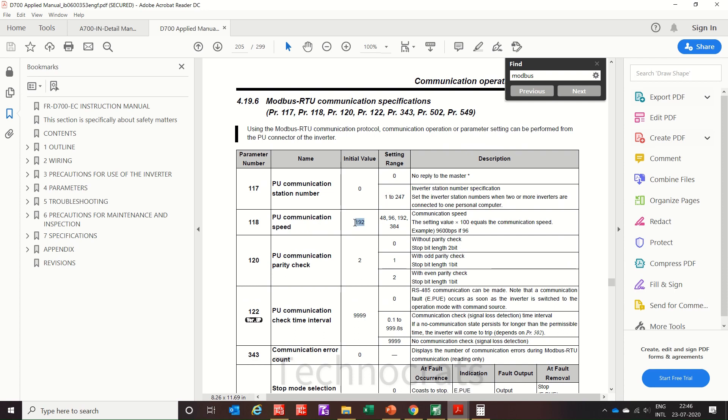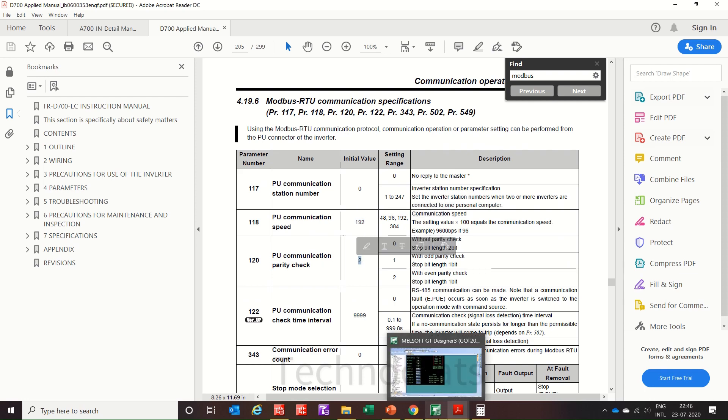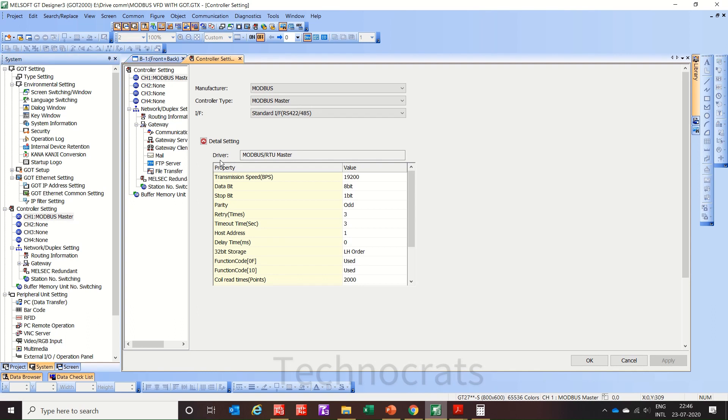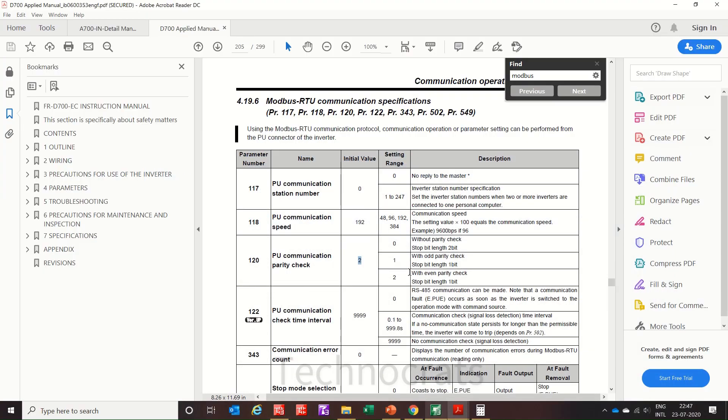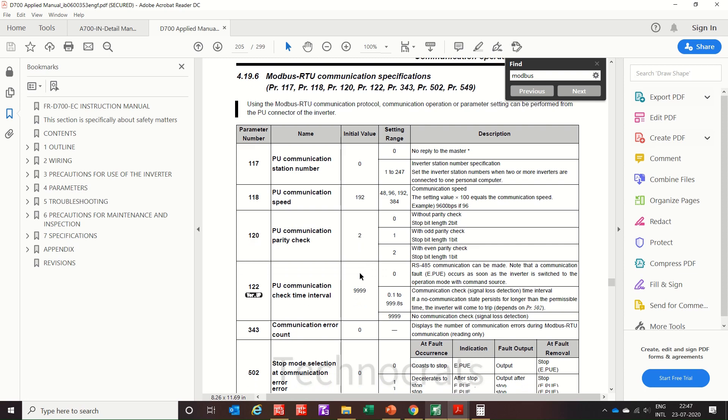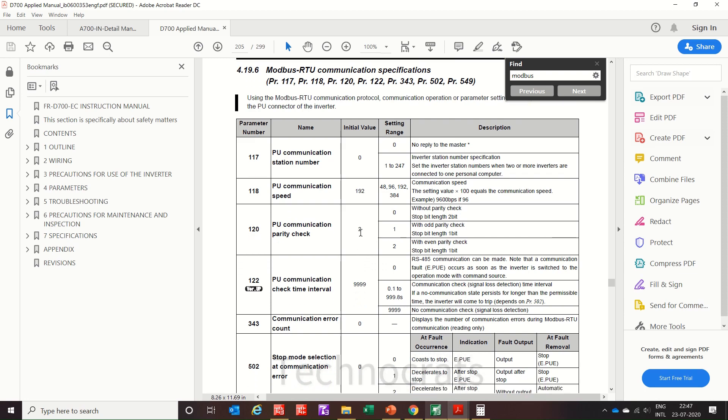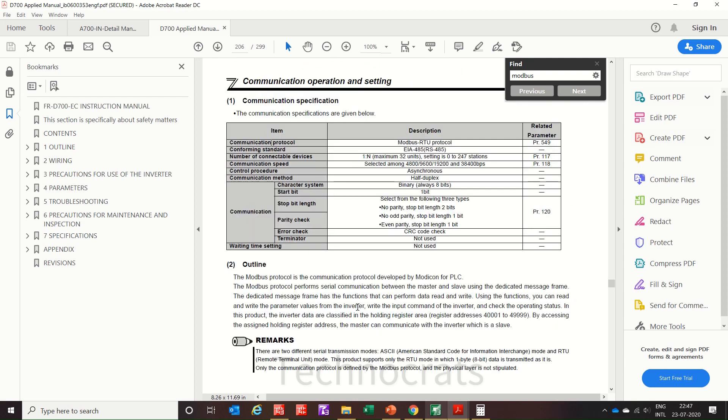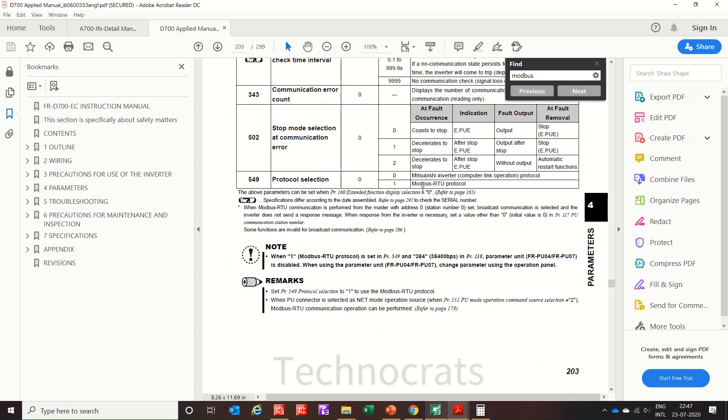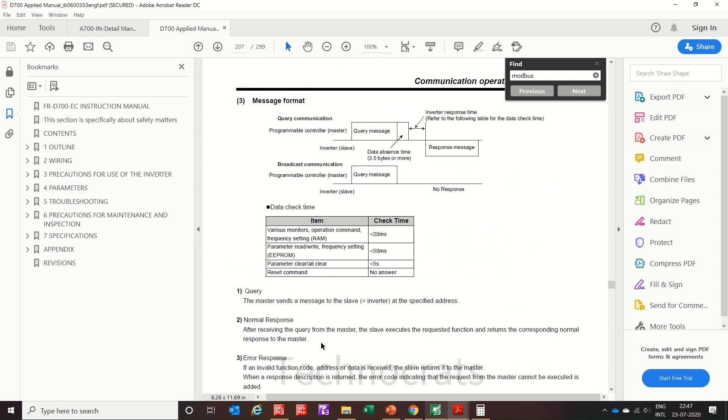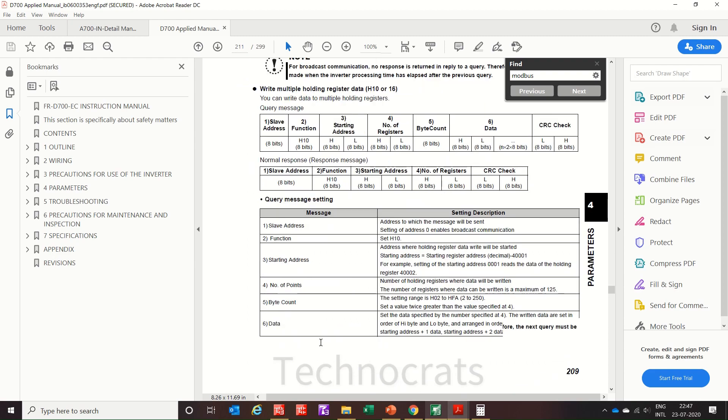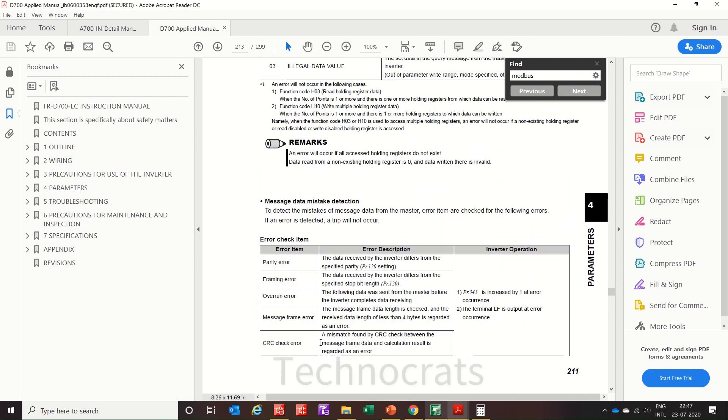This is the parity. Why I have used 192, that is default. My PU parity check is 1 in this setting. See parity I have chosen is odd, stop bit is 1, so I am using PU parity as odd, so odd part is 1, so I will use 1 here. Stop bit 1, so this will be converted to 1. Along with this I have used Modbus RTU protocol 1 here in parameter 549.